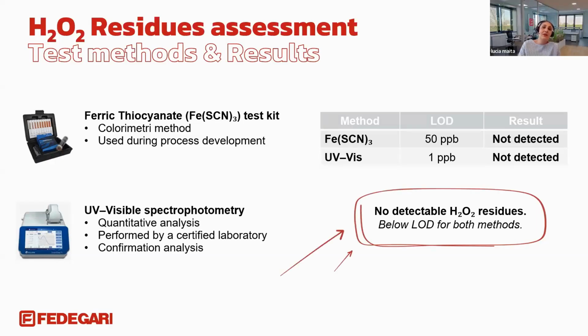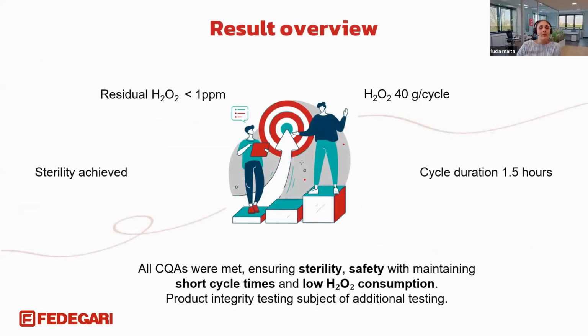This result confirmed that the parameters we use for the aeration stage are able to achieve and maintain control over residual levels. To summarize the study outcome, sterility was achieved, demonstrating that the process and the critical process parameters selected are the proper ones for this type of product. Residual hydrogen peroxide remained below the detection limit and well within the acceptance criteria. Regarding product integrity, testing is currently ongoing, with preliminary results confirming no impact on product quality. Overall the data confirm the effectiveness and the safety of the sterilization process while maintaining a short cycle time and low hydrogen peroxide consumption.